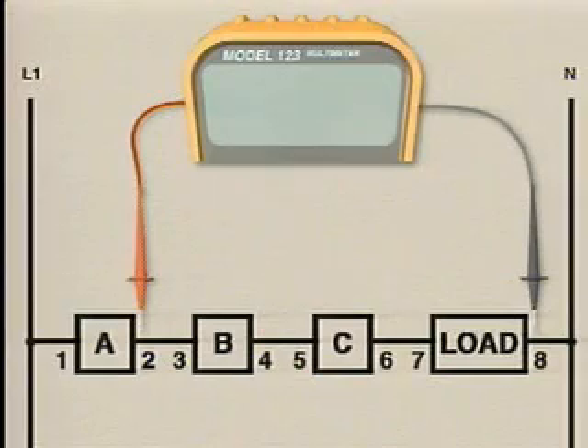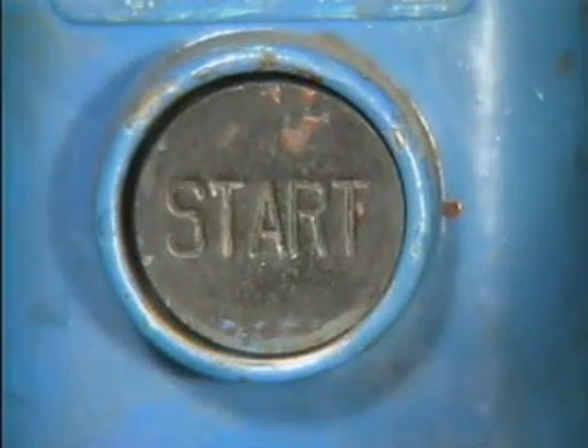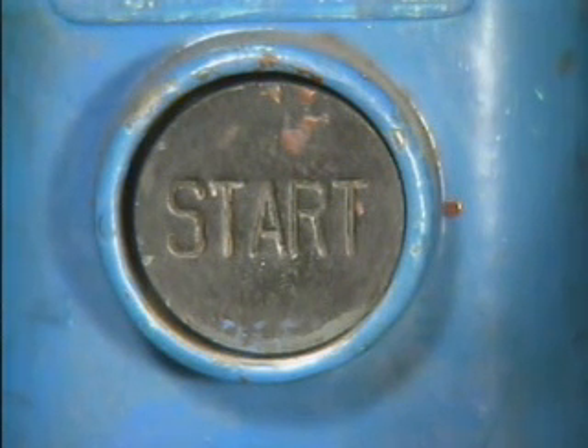There's another important point to note about making voltage checks in a circuit. Any control devices in the circuit path being checked that are normally open, such as start push-button switches, should be closed when the check is made.